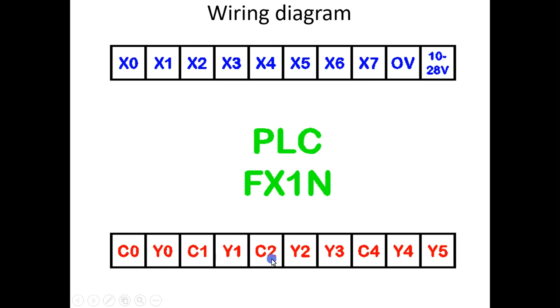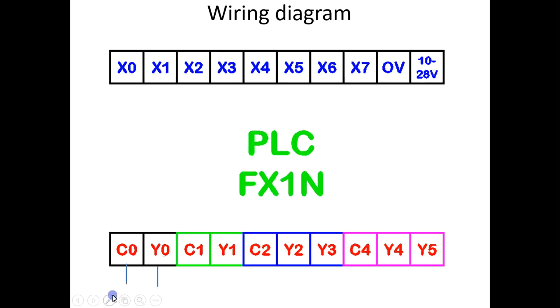Give a separate power supply to C1, and you will get that supply through Y1. Give a power supply through C2 — this power supply is common for Y2 and Y3. C4 is common for Y4 and Y5. The advantage of having different connector blocks is you can use different voltages: for example, C2 with 220V AC for light and fan through Y2 and Y3, while using C0 or C1 with 5V or 12V for other appliances.